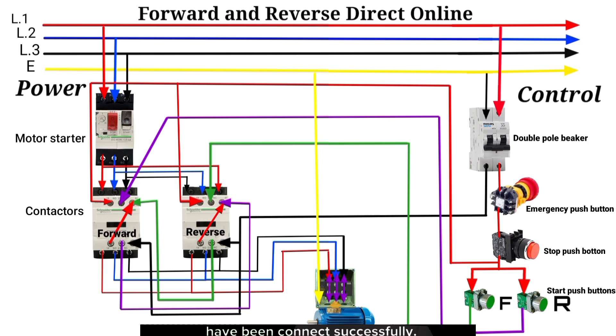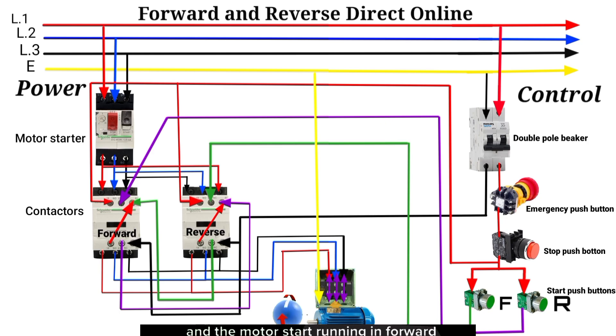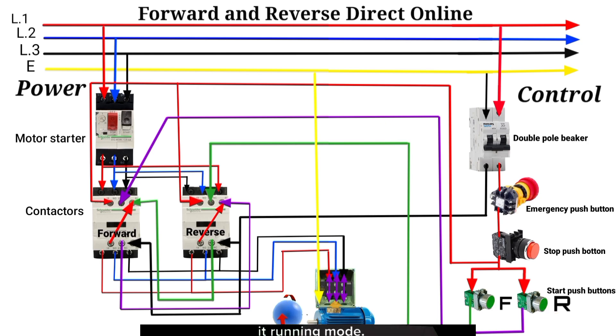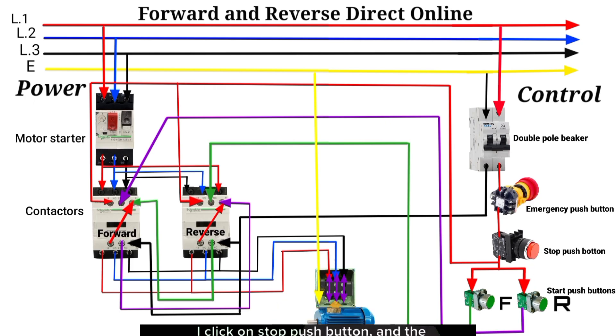With these steps, the wiring connections have been completed successfully. Now let's try out the simulator. I click the forward start push button and the motor starts running in forward mode. I click the reverse start push button and the motor does not stop or change its running mode. This happens because the forward and reverse contactors are interlocked, meaning they cannot both run at the same time.